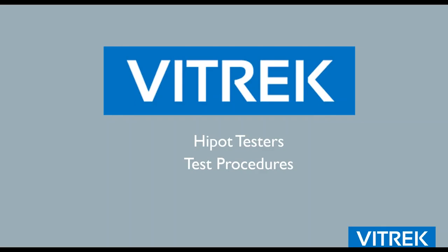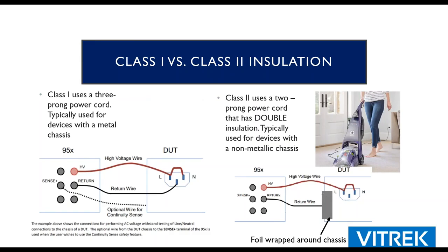So test procedure. So you order a tester, UPS drops it off, take it out of the box. Okay, what do I do now? Very common question here. So the answer is it depends on your DUT. So you have a class 1 product that's going to use a 3-wire power cord with an earth ground, and then there's a double insulated product, like a blow dryer, for example. That's actually a bad example. How about a vacuum cleaner? Because this is in the picture. Some of those are double insulated, and you're only going to have line and neutral, and it relies typically on a plastic exterior. So you don't really have a way of easily connecting to chassis ground in that situation.